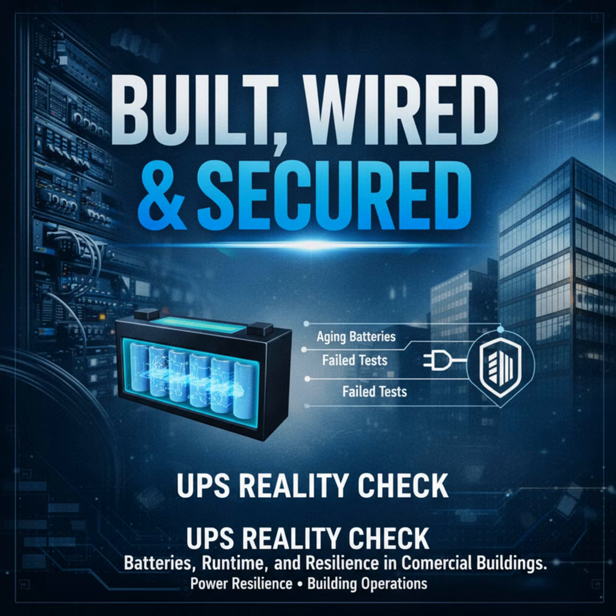Second, testing that doesn't reflect real loads. Running a UPS on a light, staged load or a short simulated outage gives a false sense of security. And third, ownership blind spots. Who documents load profiles? Who owns runtime targets? And who signs off on maintenance? When those questions are unanswered, the UPS becomes a silent single point of failure. From an operational standpoint, those blind spots are what bite you after the lights come back on.